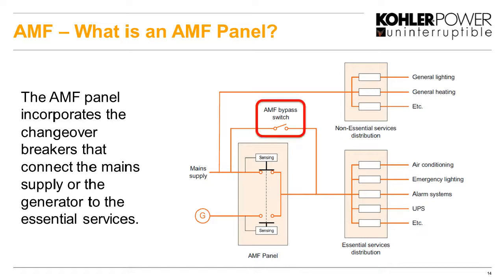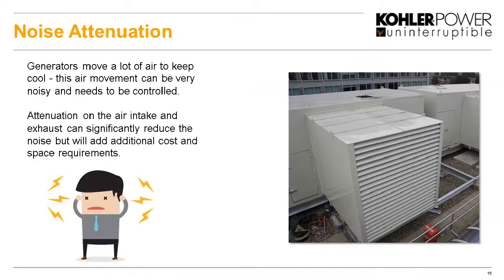What you can also see here on this drawing is that we put a bypass switch for the AMF panel. Now, it's not necessarily an absolute necessity, but it's always a good idea to have a bypass switch in your installation, and this allows for the panel to be tested, repaired, replaced, whatever you need to do. It's like having a manual bypass on a UPS. It is a very, very nice to have option that we would recommend that you put into any installation. Okay, so hopefully that tells you the basics of what an AMF panel does. Again, they all come in different sizes and shapes and varieties. But we'll move on. Noise attenuation.